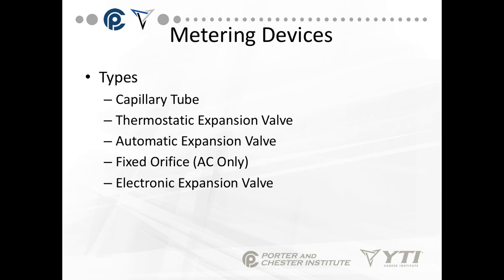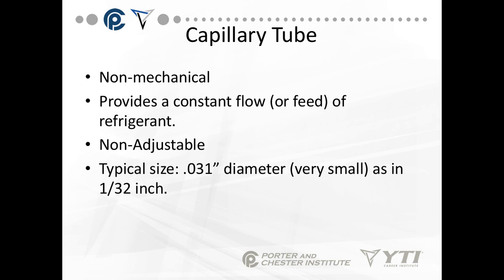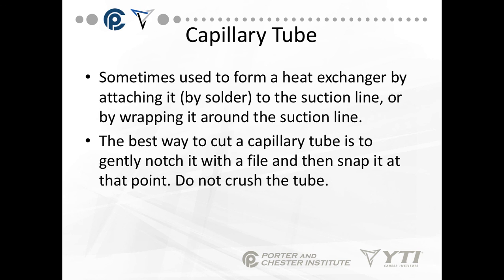We have several types of metering devices: the capillary tube, the thermostatic expansion valve (TXV), the automatic expansion valve, a fixed orifice seen in air conditioning and heat pumps only, and an electronic expansion valve. The capillary tube is one of the few that's non-mechanical. It provides a constant flow of refrigerant, is non-adjustable, and its typical size is 0.031 inches in diameter — extremely small, about 1/32nd of an inch. It's sometimes used to form a heat exchanger by attaching it by solder to the suction line or by wrapping it around the suction line.